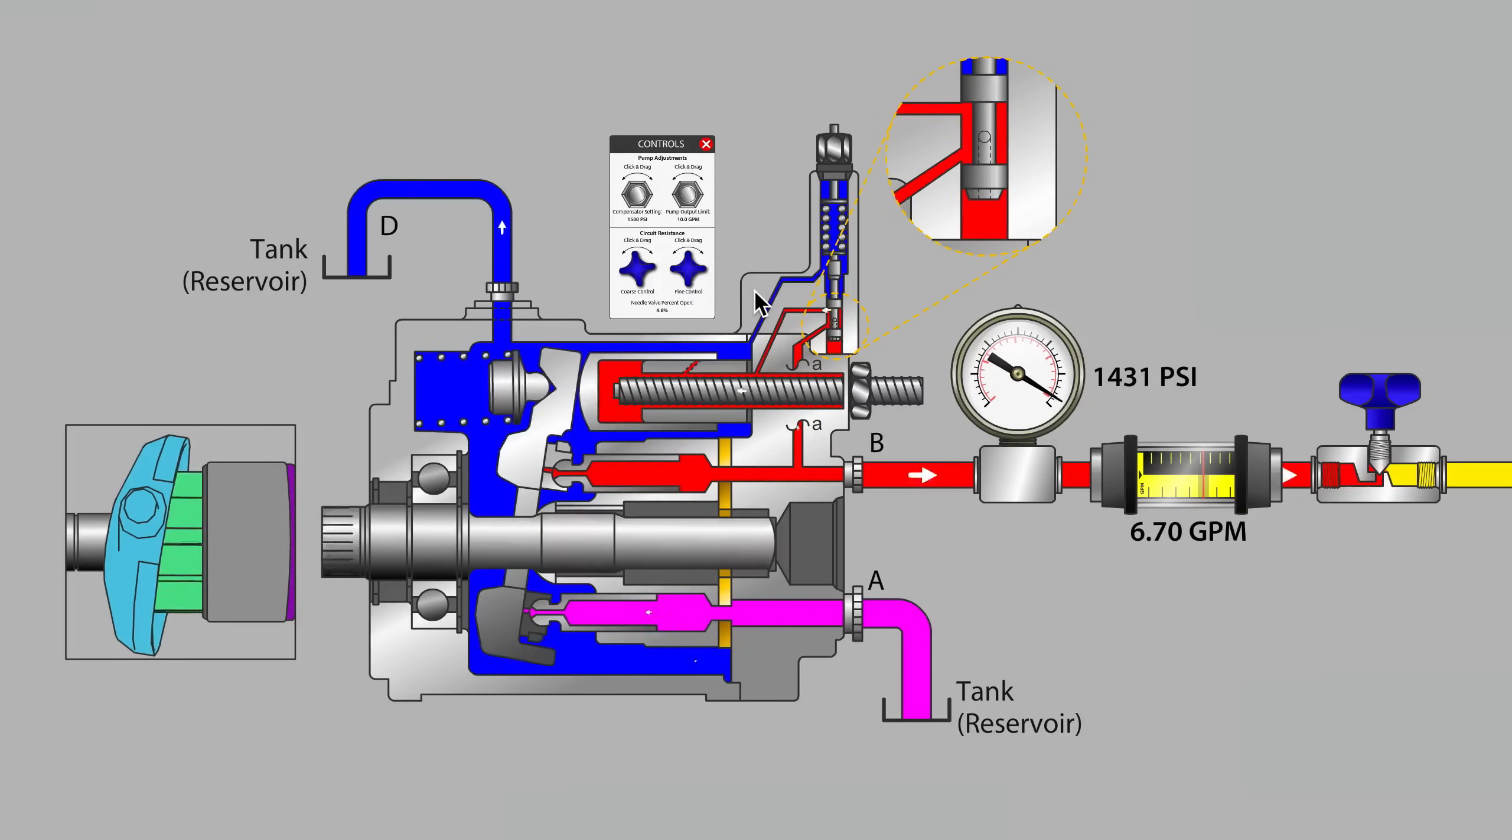And then also consider the pressure compensator, sometimes referred to generically as the controller on the pump. In most cases the controller on the pump requires a flow of fluid in order to carry out its basic functions and indeed you could see flow is taking place.